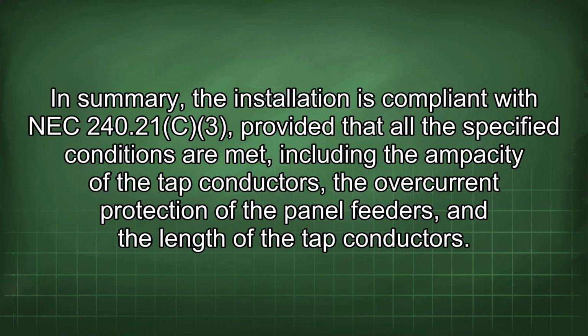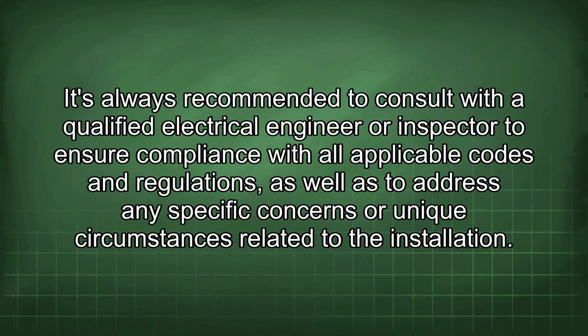240.21(c)(3), provided that all the specified conditions are met, including the ampacity of the tap conductors, the overcurrent protection of the panel feeders, and the length of the tap conductors. It's always recommended to consult with a qualified electrical engineer or inspector to ensure compliance with all applicable codes and regulations, as well as to address any specific concerns or unique circumstances related to the installation.